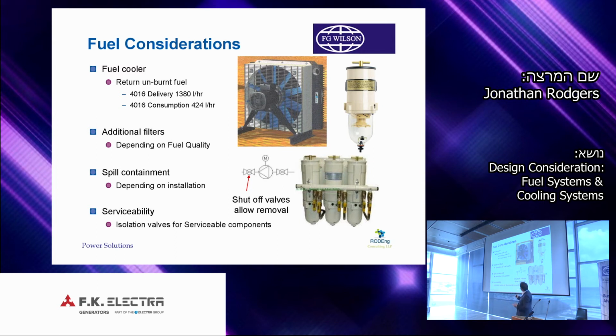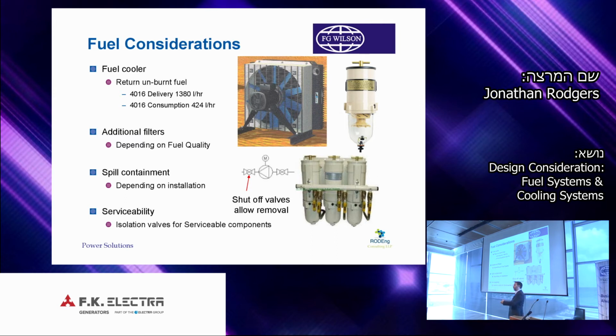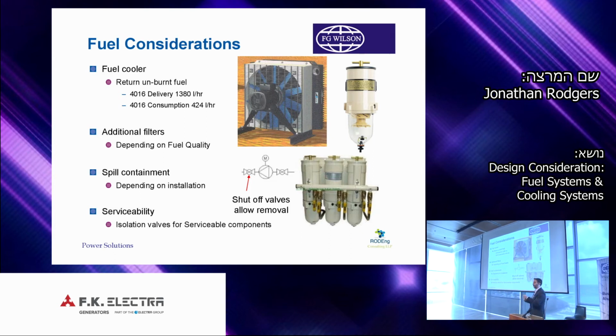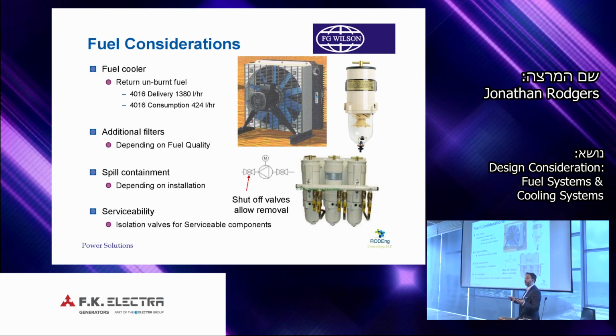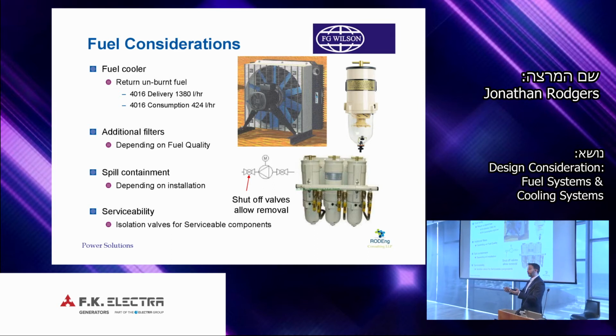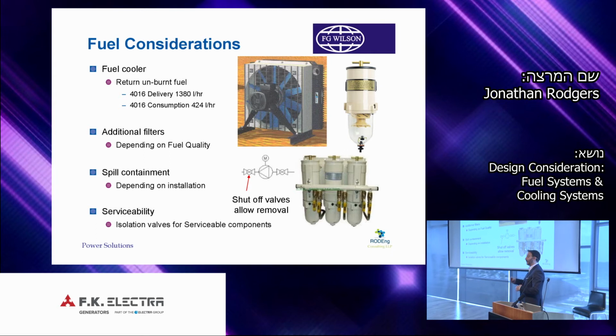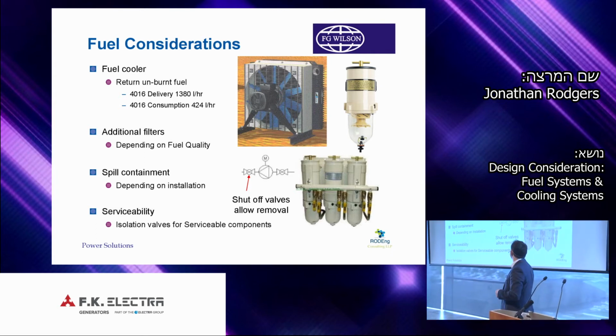So we have 956 litres returning back to the tank. We have more coming back to the tank than we have burnt in the cylinder. That fuel is used for lubrication and also to remove heat. So the fuel returning comes back hot, and we need that fuel temperature to be controlled, because if we supply fuel back to the injector at too high a temperature, the injector seal will lock and seize. We use fuel coolers to reduce the heat from the returning fuel, and that allows us to use all of the volume of fuel in the tank.